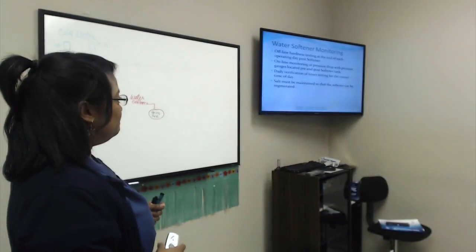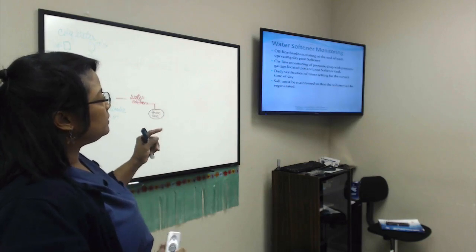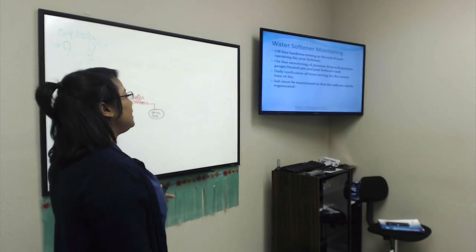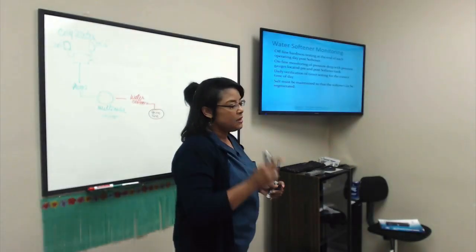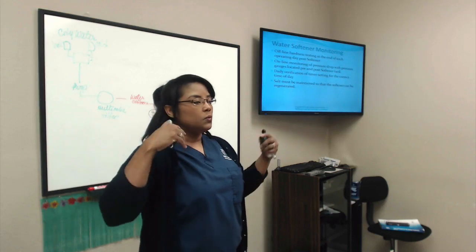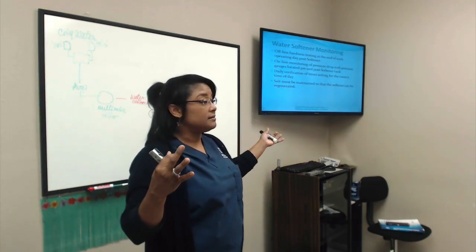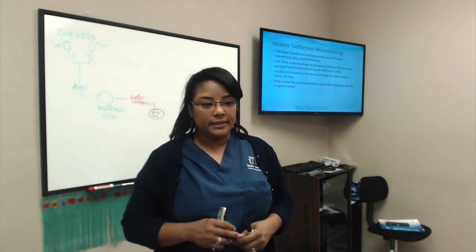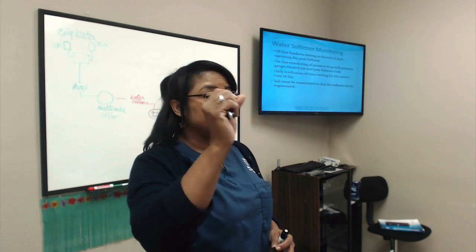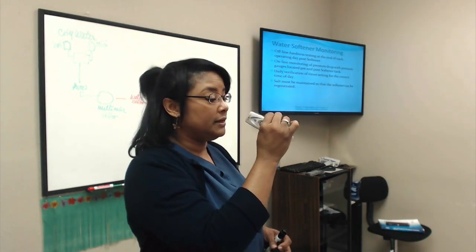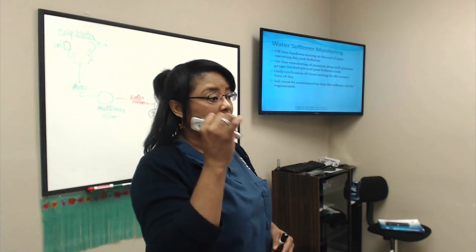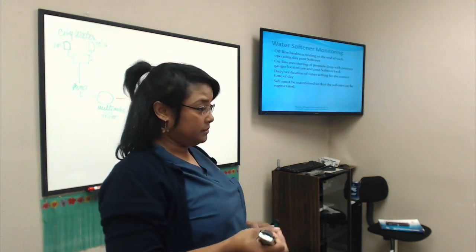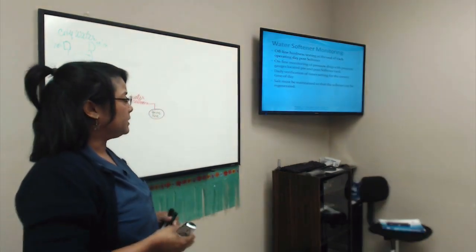Okay, so offline means when we're not using it, okay? So offline hardness testing at the end of each operating day, post softener. So what this means is, when do we test the softener? At the end of every operating day. Now, there are many clinics that are taking an extra step as precaution, and they're testing in the morning and at night. So if you choose morning and night, it's correct, okay?